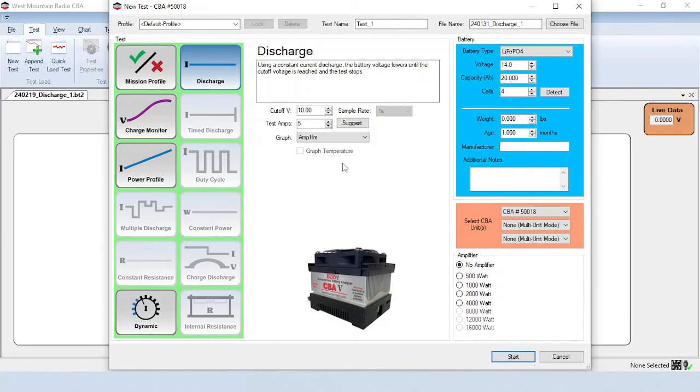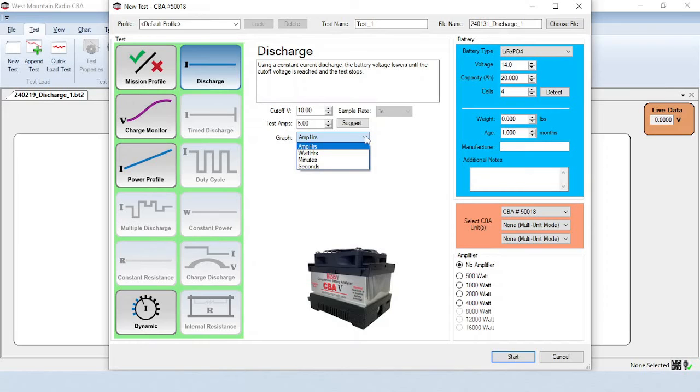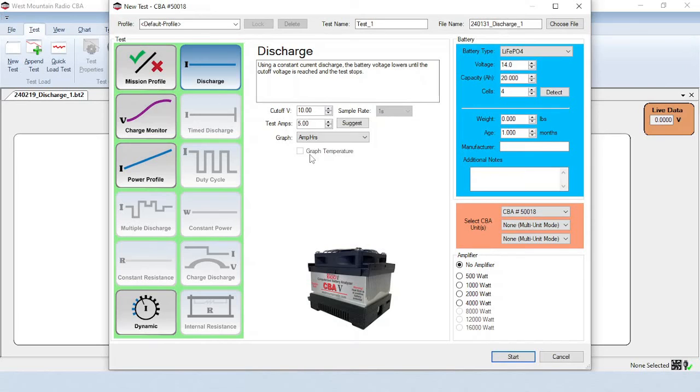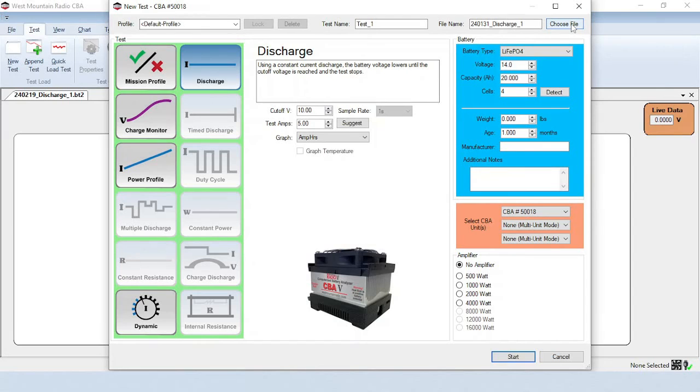The graph can be displayed in amp hours, watt hours, minutes, or seconds. If you have the extended software and a temperature probe connected to the CBA, you can check the box to graph the temperature during the test. At the top is where you can fill in the test name, and the file name and location for where the test will be saved. Double-check to ensure all settings are correct, then press Start.